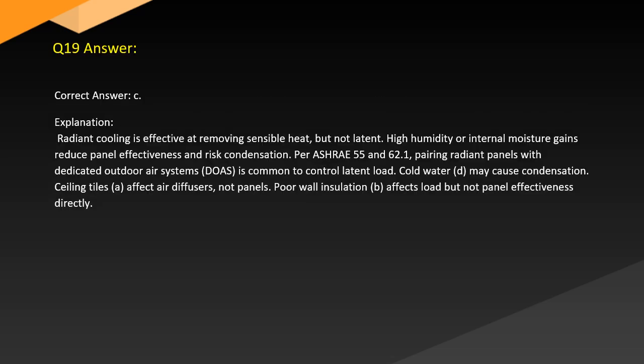Answer. Correct answer: C. Explanation. Radiant cooling is effective at removing sensible heat, but not latent. High humidity or internal moisture gains reduce panel effectiveness and risk condensation. Per ASHRAE 55 and 62.1, pairing radiant panels with dedicated outdoor air systems (DOAS) is common to control latent load. Cold water may cause condensation. Ceiling tiles affect air diffusers, not panels. Poor insulation affects load but not panel effectiveness directly.